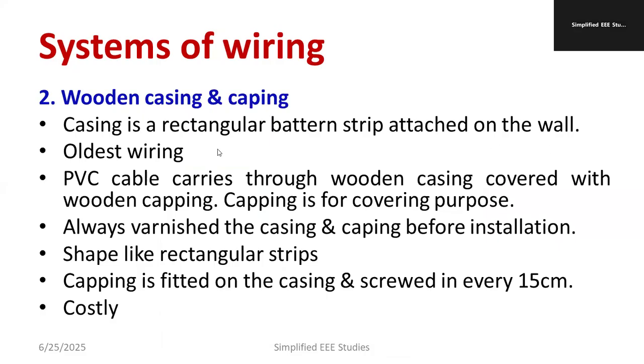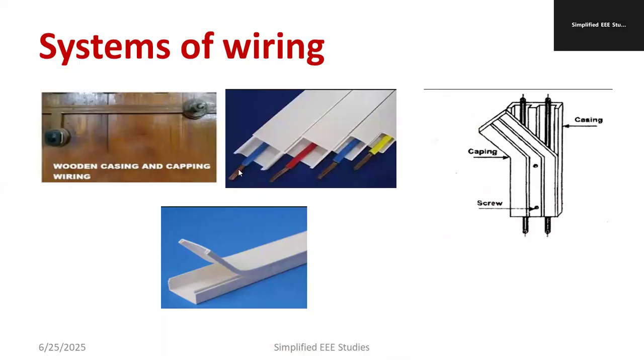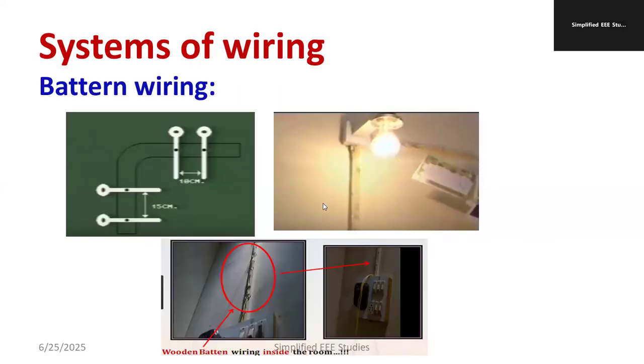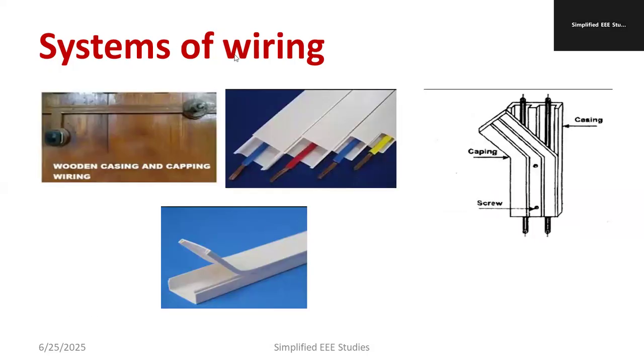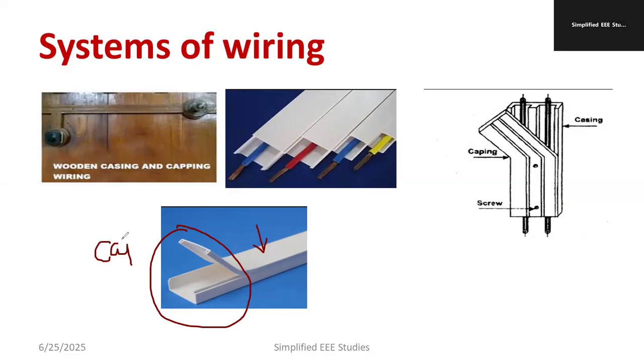Similar to batten wiring, we have wooden casing and caping wiring. Casing is a rectangular batten strip attached on the board, with an opening — that's a specialty. In batten wiring there is no provision to open for maintenance, but wooden casing and caping provides that facility. It is the oldest type of wiring, used in old buildings and palaces. The PVC cable carries through the wooden casing, covered with the wooden caping.